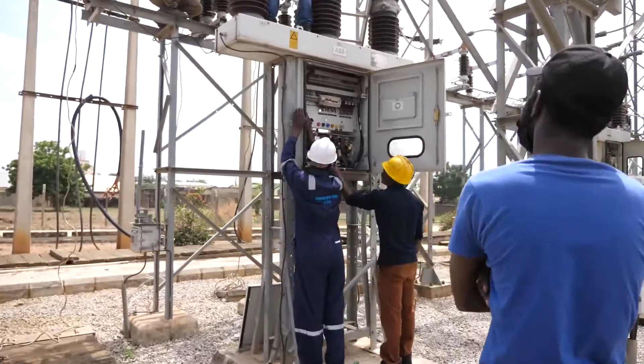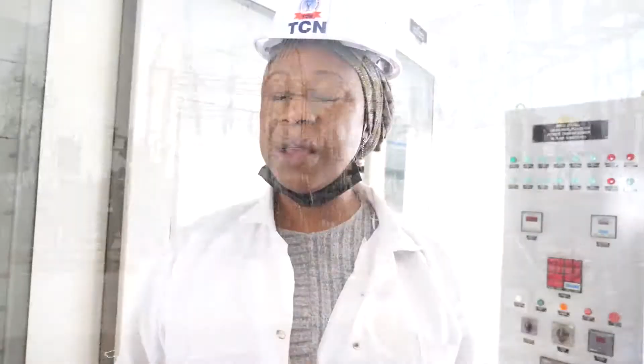If everything is okay, we restore back. If anything needs to be changed, we have so many spares that come with us; we change them and make sure things are working properly. After the annual maintenance, the TCN engineering experts said it will be a good boost to the stability of the transmission system. We expect the system to be more stable and reliable. That's mainly what we want. And if there is a fault, only those that need to be isolated are isolated, not the whole system. It's mainly reliability and stability of the system.